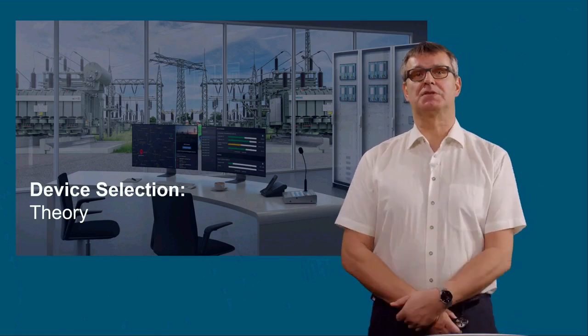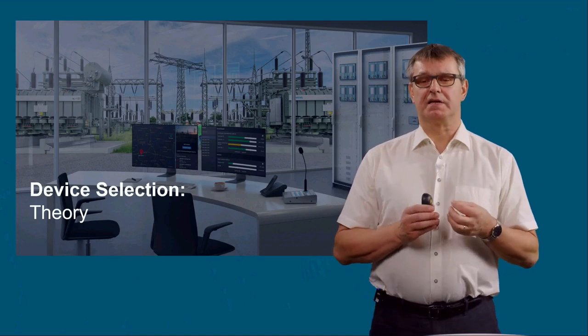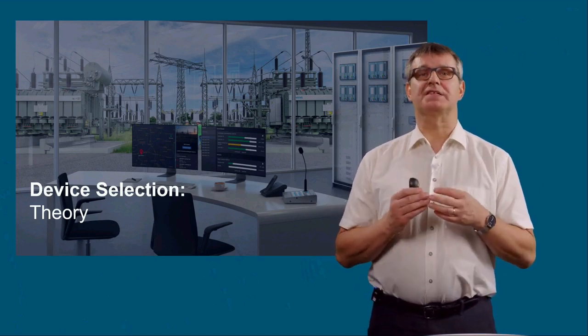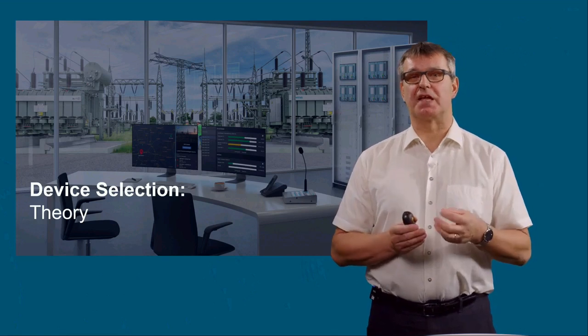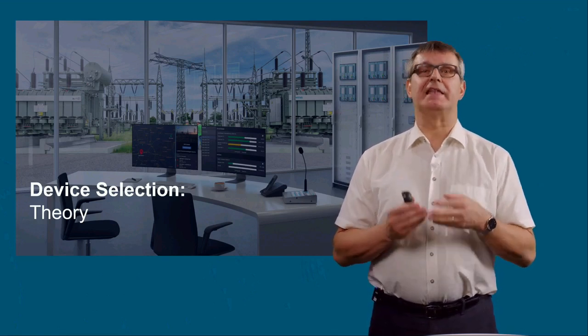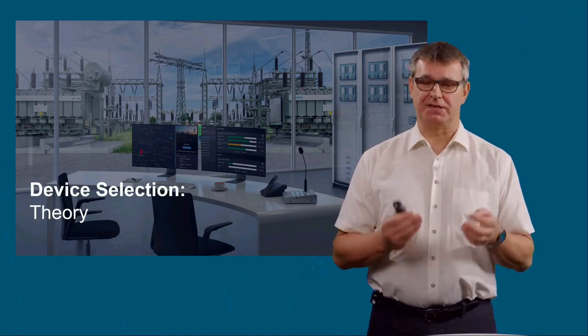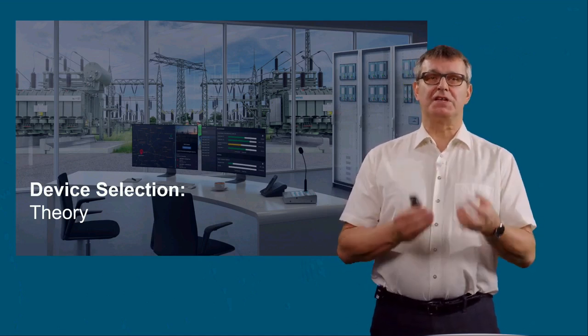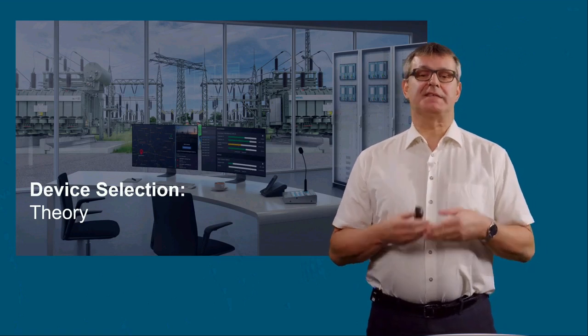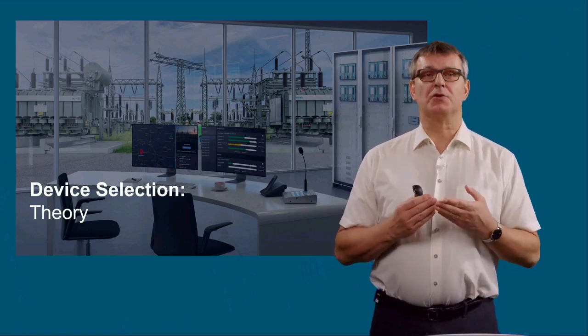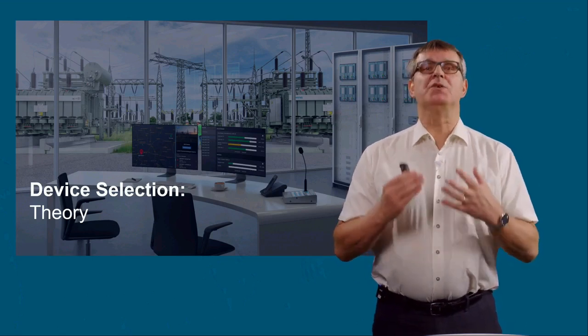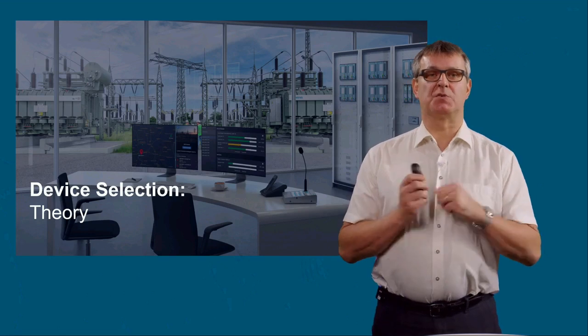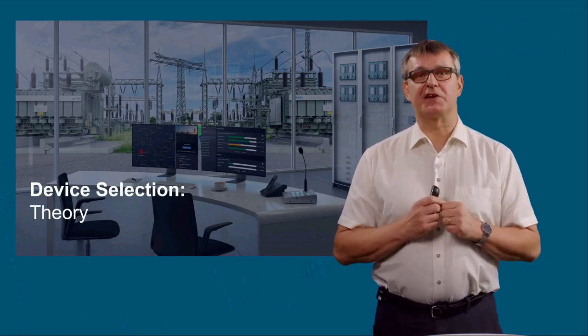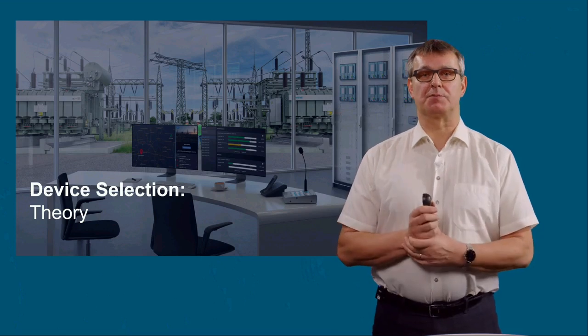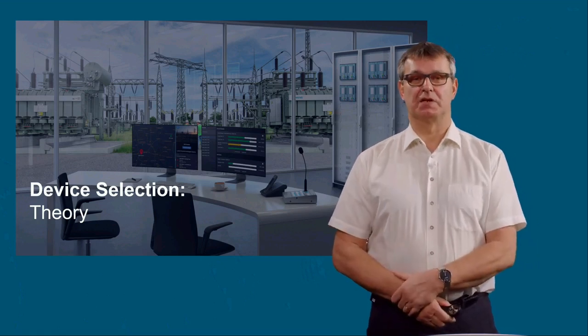But of course, what is possible, as each modular SIPROTEC 5 device can be used as a bay unit for the distributed busbar protection. And so, of course, you can use a line differential protection device, a 7SL86, 87, with the integrated line differential protection. And then you can integrate it in the functionality of the bay unit of the distributed busbar protection. This is possible, to take a line differential protection device as a bay unit for the distributed busbar protection, and then you have the line differential protection. Maybe this question was more in this direction.